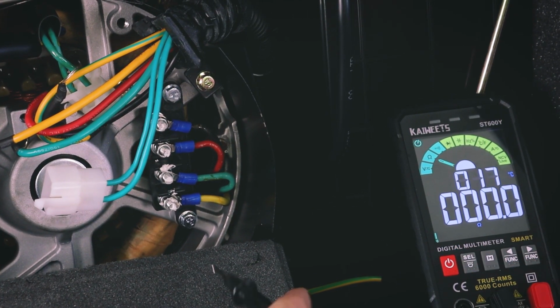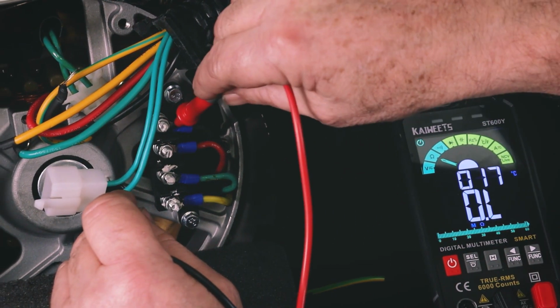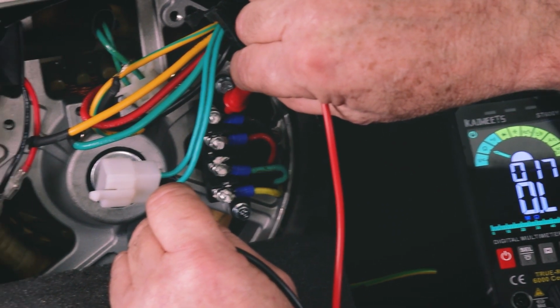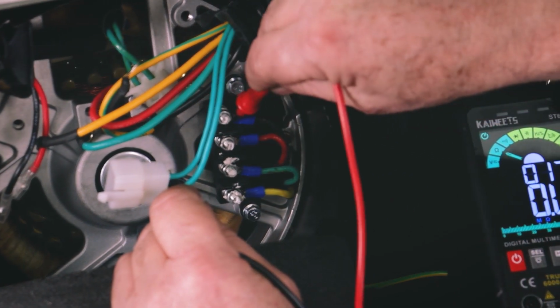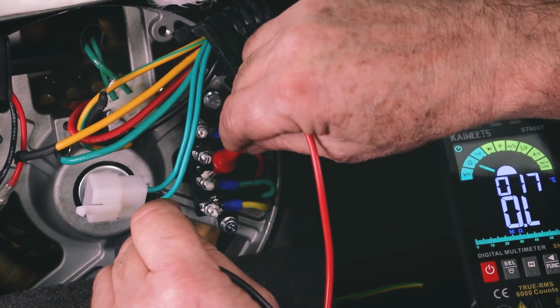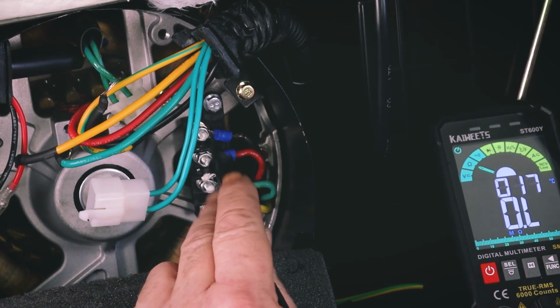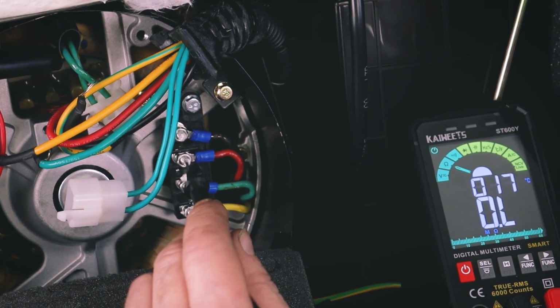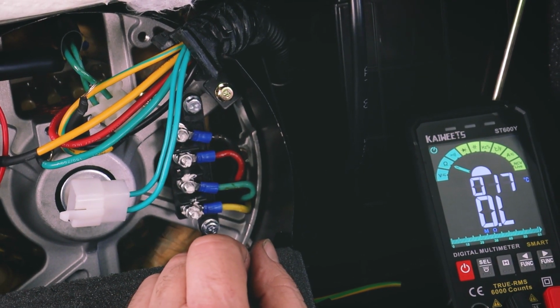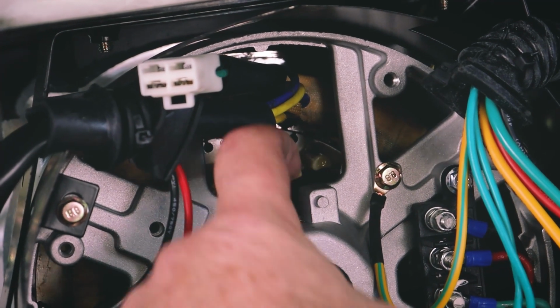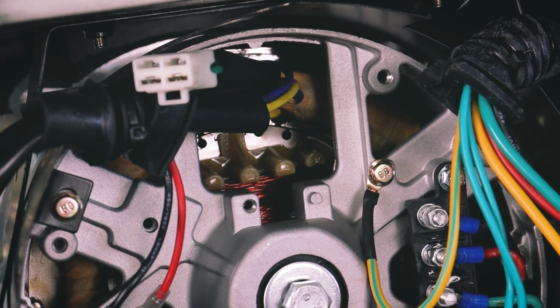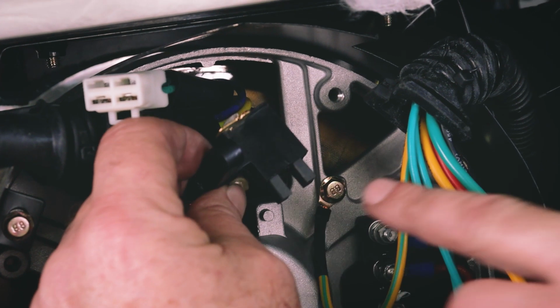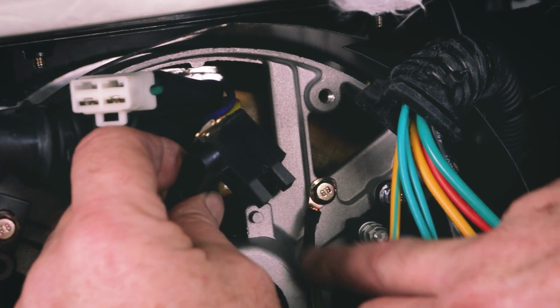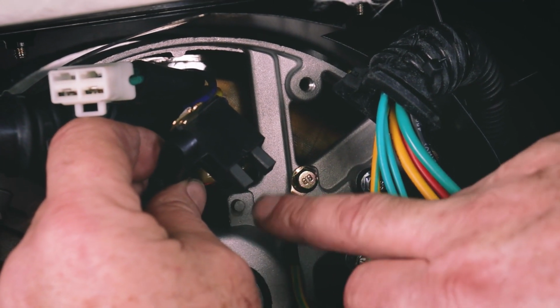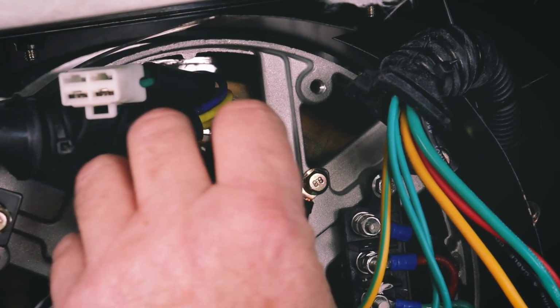0. Okay. So none of these must be touching ground. So that's another check we can do. Touching on the main body, touch all 4 terminals, absolutely nothing touching to ground. If anything is touching to ground, then again, we're in alternator change territory. So it's very difficult for me to show you, but our brushes, when they were in position, ran on what we call slip rings, 2 brass rings which are insulated from each other, and these run on those rings.